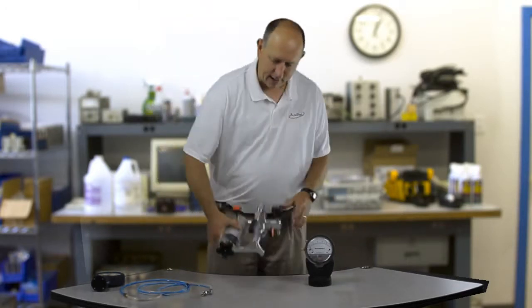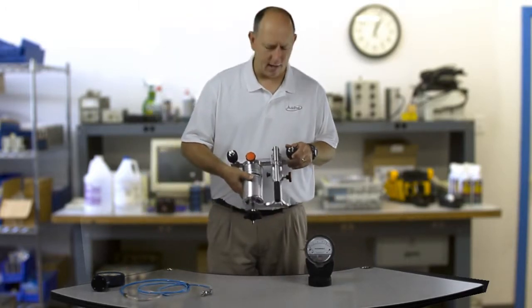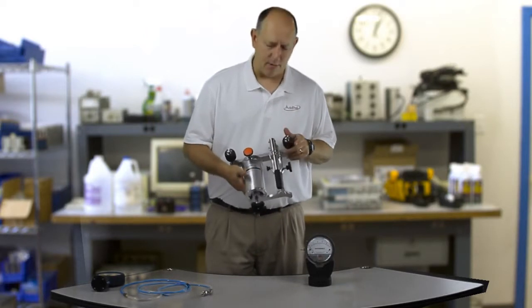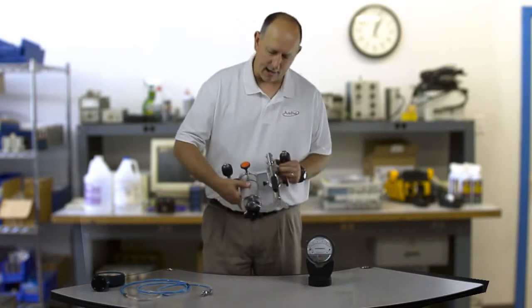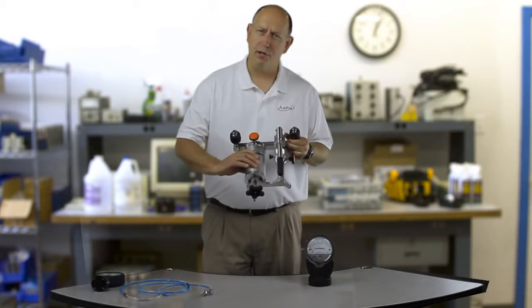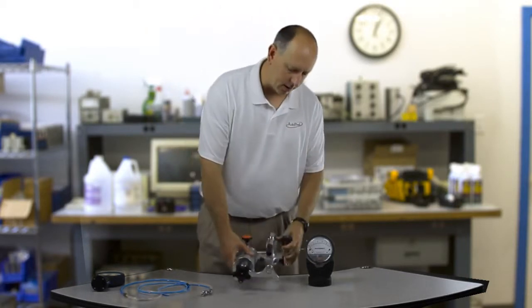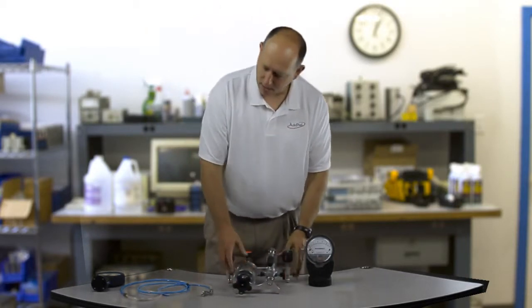This is an Additel ADT912A, a vacuum to 60 psi pump, and it has this really fine adjust for low pressure differential pressure calibration. I'm going to show it to you here today.